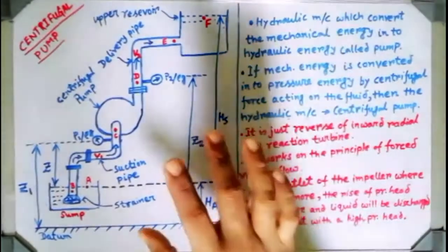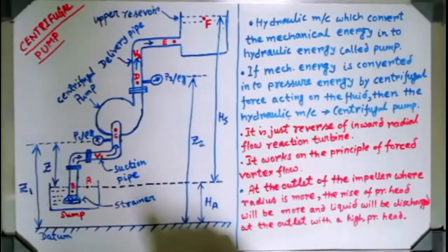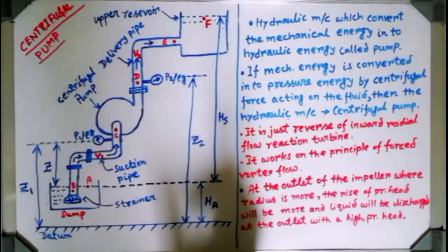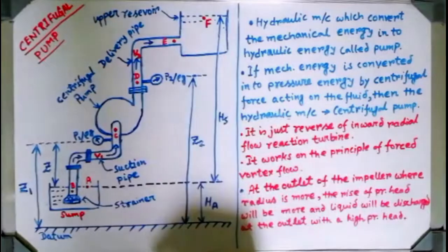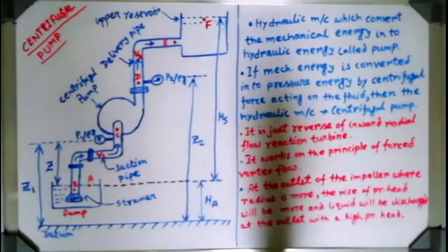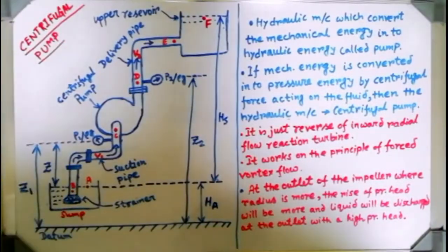If it is a reciprocating pump, then the working principle will be the reciprocating motion of a piston inside a cylinder. Here it is not a piston-cylinder arrangement. Inside this casing a rotor will be there. When that rotor rotates with a high speed, then a centrifugal force will be generated, and that centrifugal force basically raises the pressure of that working fluid.